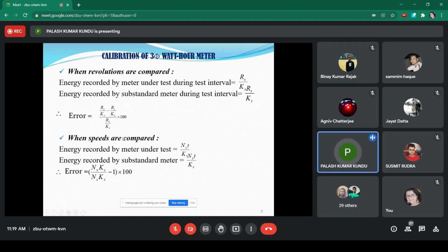Now, when the speed is compared, it is not generally followed. When the speeds are compared, then the formula for the error computation is different according to this equation. Both computation rules can be used here under the short time test. So the short time test actually determines the error in the disc rotation.